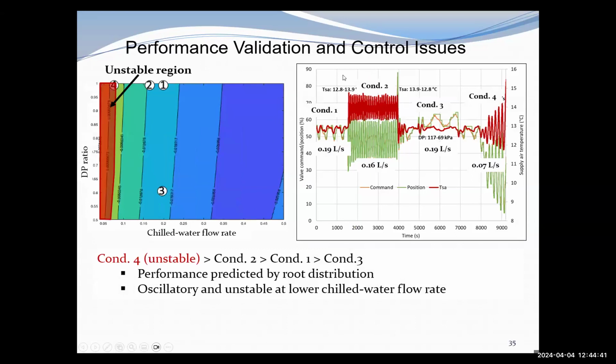And here we conducted the test. The right figure shows the test result. You can see on condition 4, when the real part becomes positive, the system is unstable. And from the test result, the system is unstable here. Also under condition 2, it has a relatively smaller negative real part, and the test result shows oscillation here. And under condition 3, it has the largest negative real part, and it has the most stable performance here.